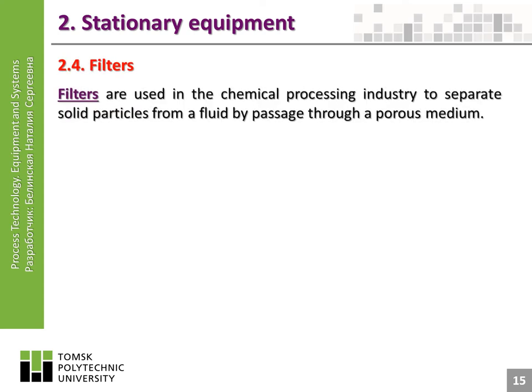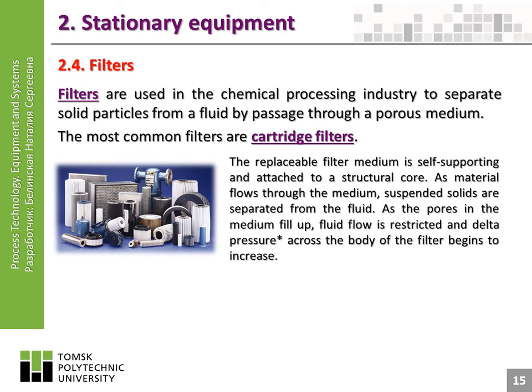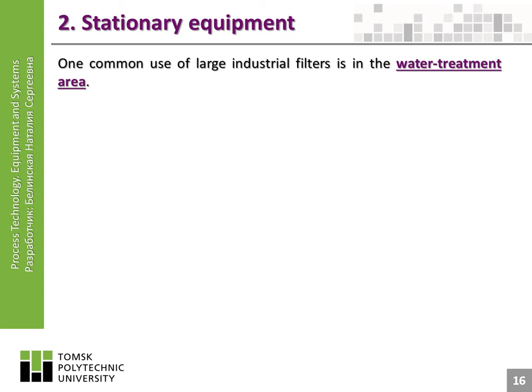Filters are used in the chemical processing industry to separate solid particles from a fluid by passage through a porous medium. The most common filters are cartridge filters. The replaceable filter medium is self-supporting and attached to a structural core. As material flows through the medium, suspended solids are separated from the fluid. As the pores fill up, fluid flow is restricted and delta pressure across the filter begins to increase. Redundant filter systems allow a technician to switch to a clean filter and safely remove the dirty cartridges.